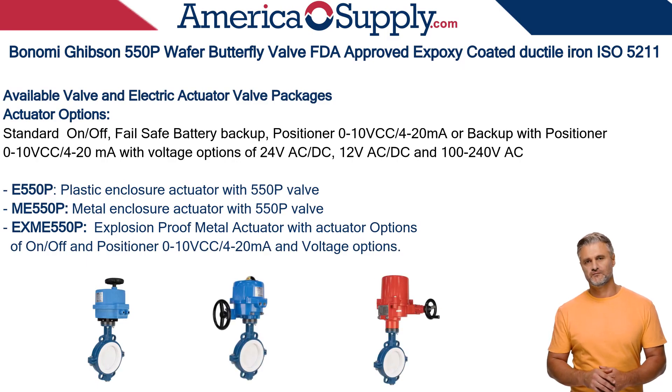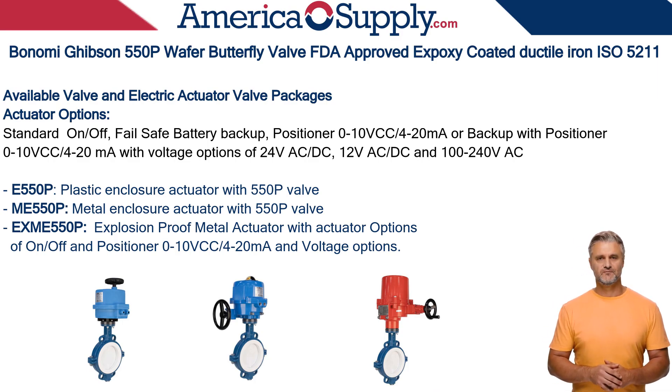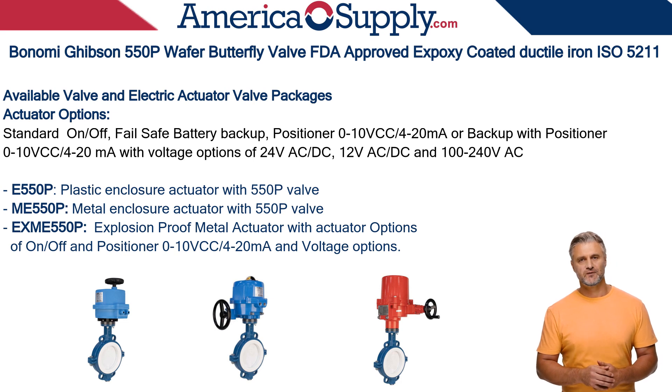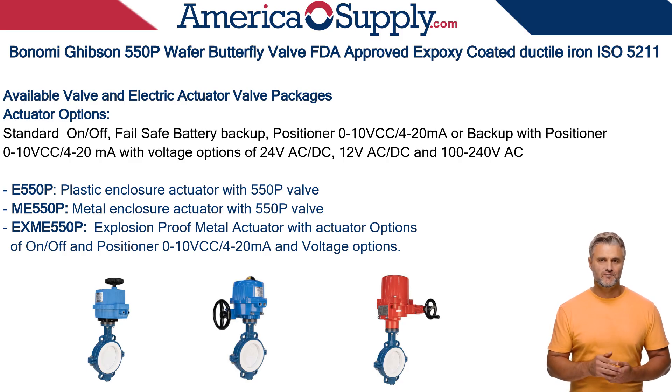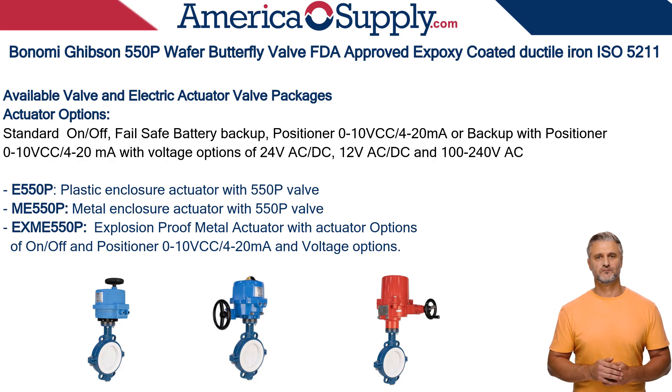The Gibson 550P valve is also available with Valbia select electric and pneumatic actuators. For both electric and pneumatic actuator packages, the actuators are selected according to valve size for optimal performance and power. The electric actuator packages are the E550P with plastic enclosure actuator and actuation options of standard on-off, fail-safe battery backup, positioner 0-10 VDC / 4-20 mA or backup with positioner, with voltage options of 24 VAC/DC, 12 VAC/DC, and 100 to 240 VAC/DC. The ME550P features a metal enclosure actuator with identical actuator options. The EXME550P is equipped with an explosion-proof actuator with options of standard on-off and positioner 0-10 VDC / 4-20 mA.